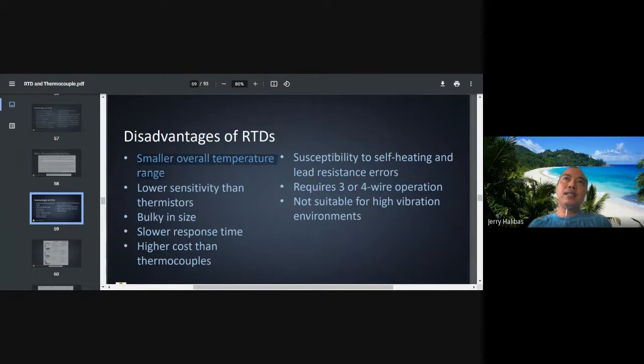Way back when I was still in the field, there was a certain requirement in an oil refinery. They reached about 300 degrees centigrade, so they were using a thermocouple rather than an RTD. Though it is within the range of an RTD, it is not that effective. Usually an RTD does not go beyond 200 degrees centigrade. But in an oil refinery, it can reach even more than 300. So that's why a smaller overall temperature range is a disadvantage.